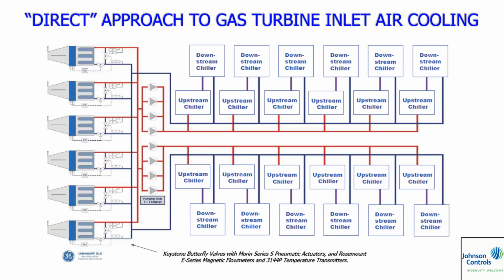All right, and so with the air-cooled chillers, we had these air-cooled chillers. Remember, air-cooled heat exchanger, which is a fin and tube heat exchanger using air for heat rejection. The evaporator was a shell and tube heat exchanger, ASME vessel. We had them in series, so we had an upstream and a downstream chiller because we had a pretty wide delta T on the water. The wider the delta T, the smaller your pipe. So we were designing this so we could put it together, but also try to reduce total installed costs. So anytime you can do a wider delta T on water, that's to your advantage. So we had all of the evaporators in series. So that's what you're looking at here.